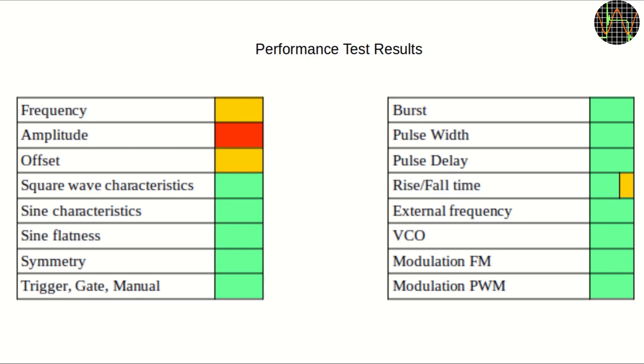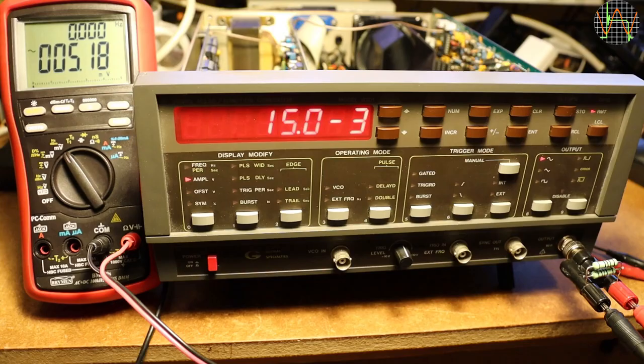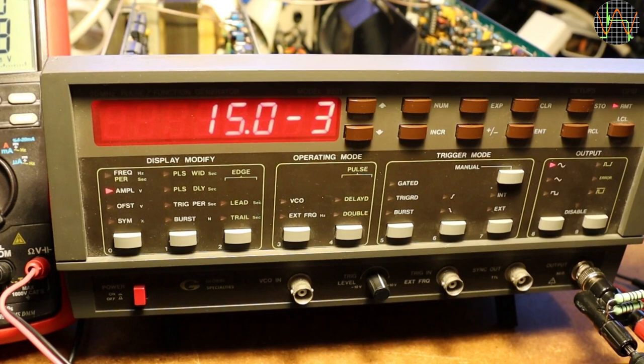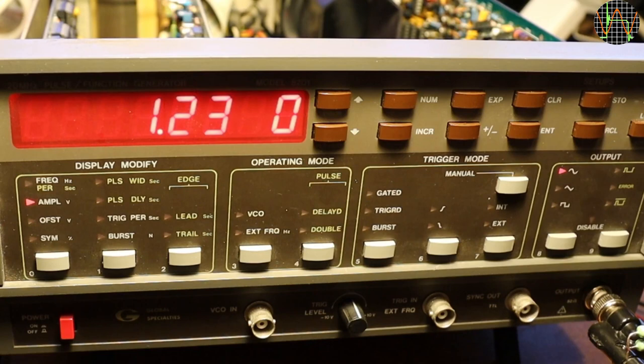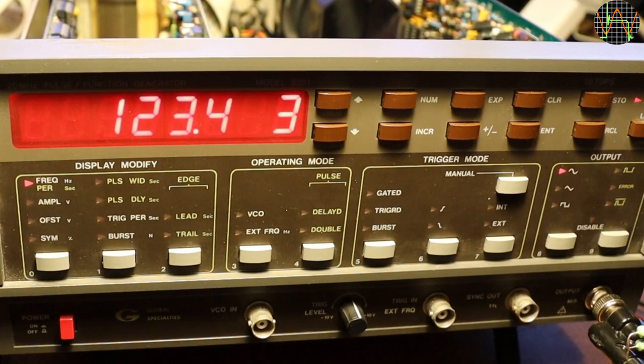Before I move on to the necessary adjustment, a quick sidetrack. It turns out that GPIB remote interface is working as well. For example, setting the amplitude to 1.23V peak-to-peak. Changing the display to show frequency which happens to be 1kHz. Changing frequency to 123.4kHz. This is a huge time saver when running tests considering the clunky front panel interface, so on with the adjustments of the low frequencies first.